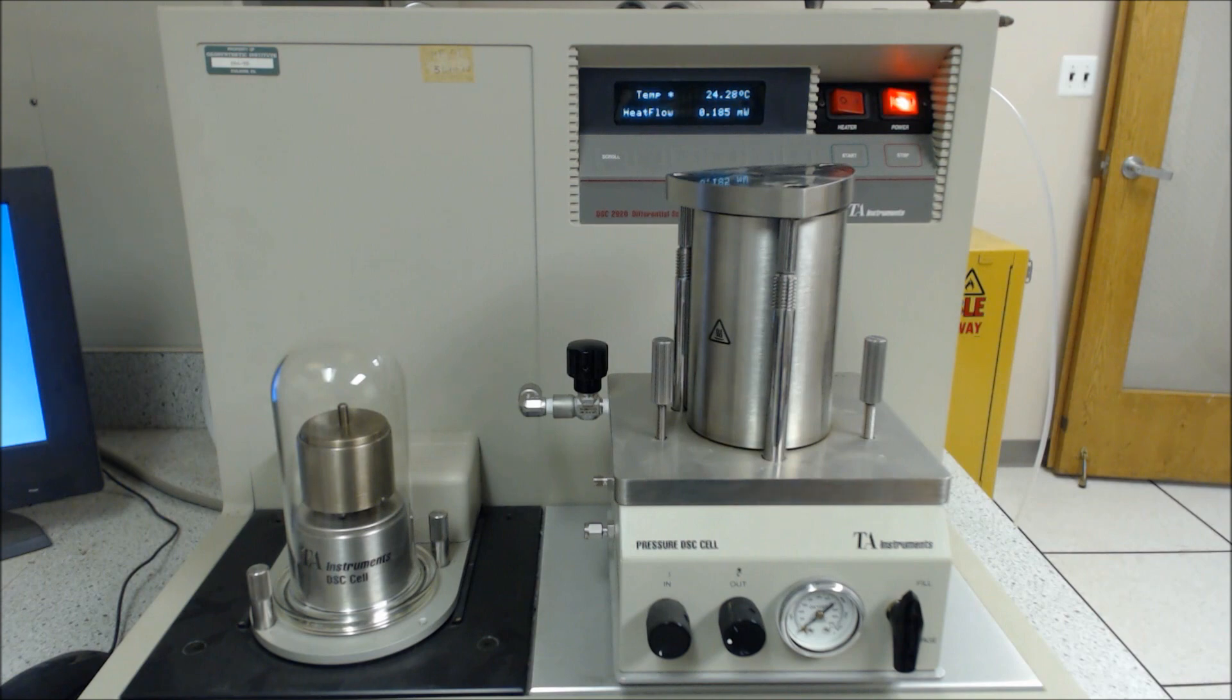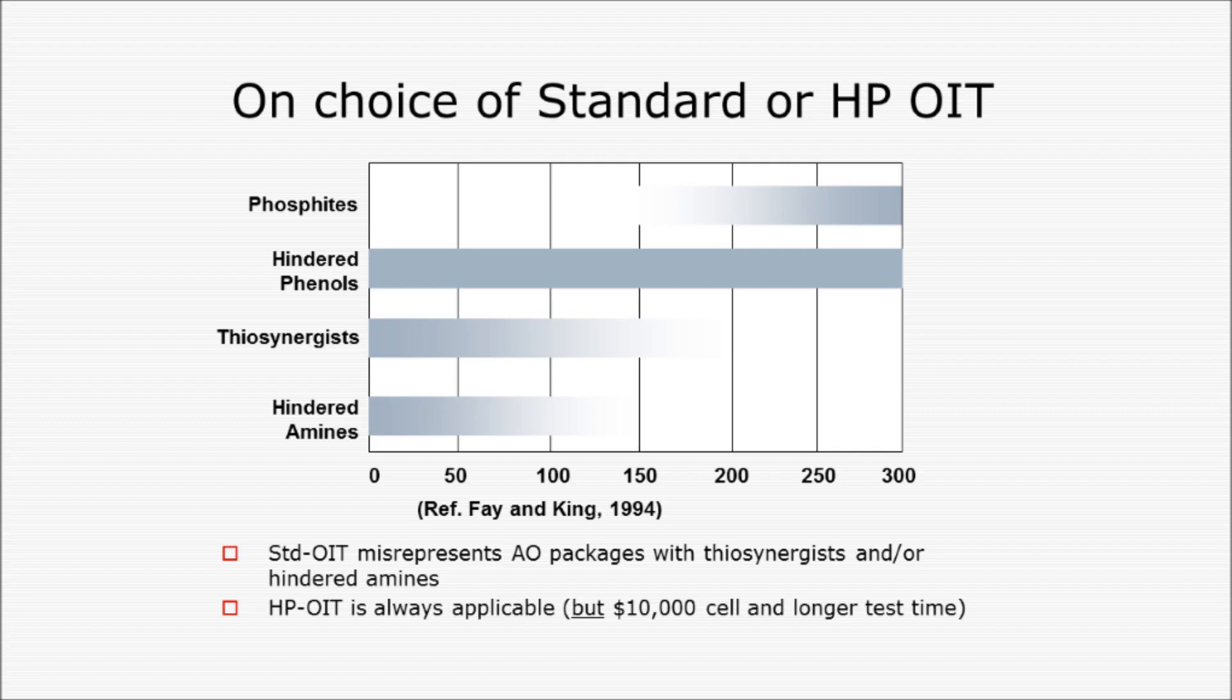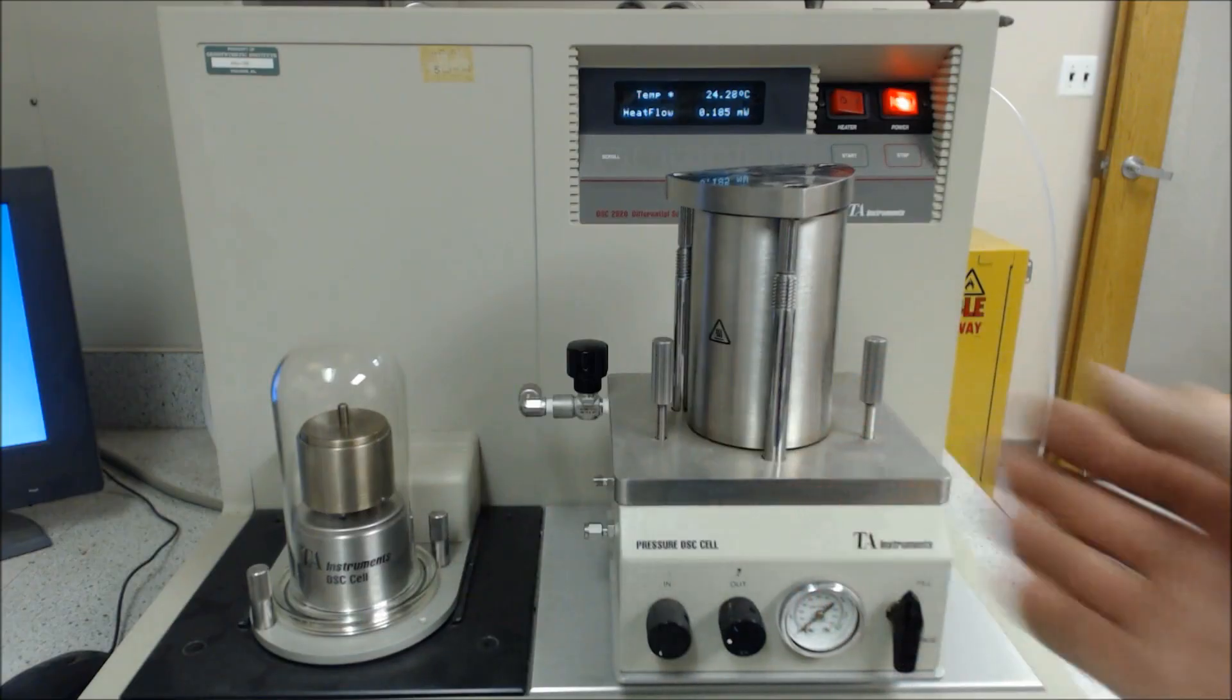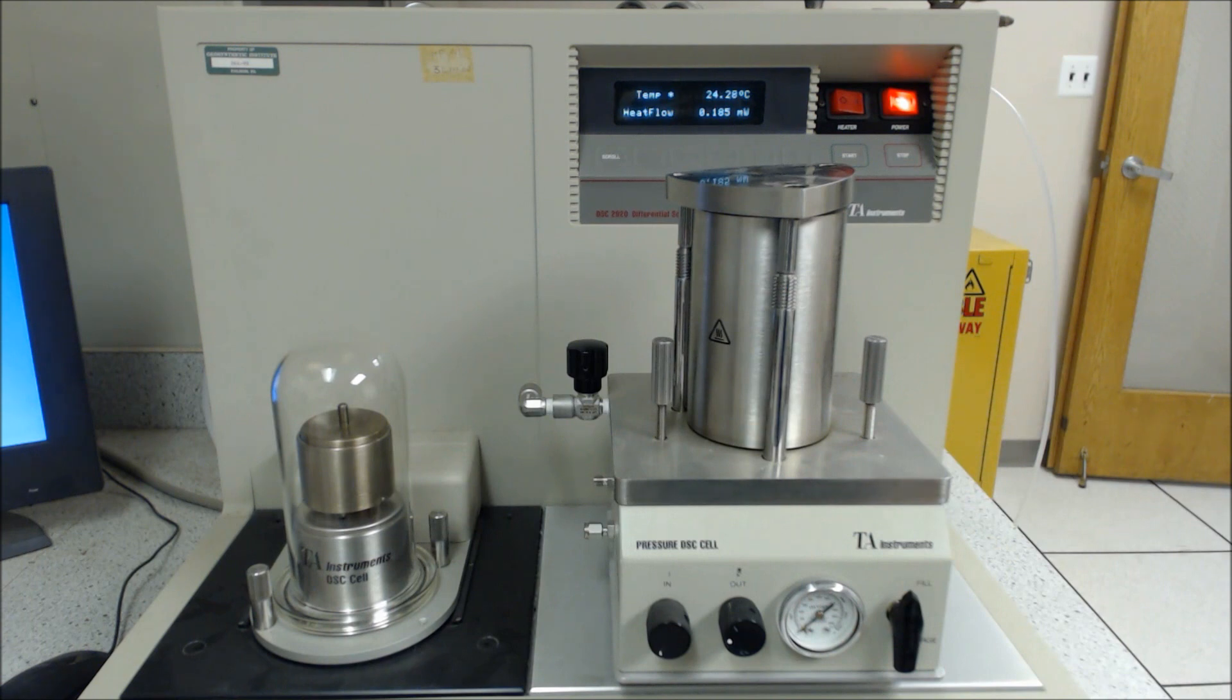On the left you can see the DSC cell used for running an OIT test at a pressure of 34 kilopascals or 5 psi, and on the right you can see the high pressure cell used to run HP OIT at a pressure of 3400 kilopascals or 500 psi.